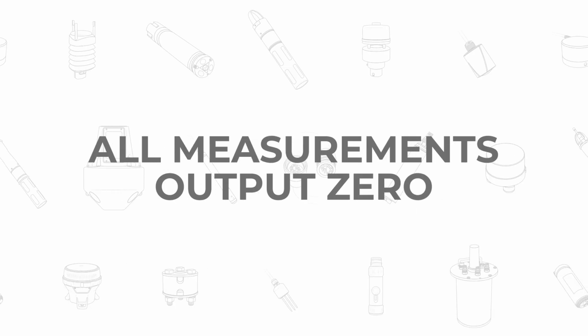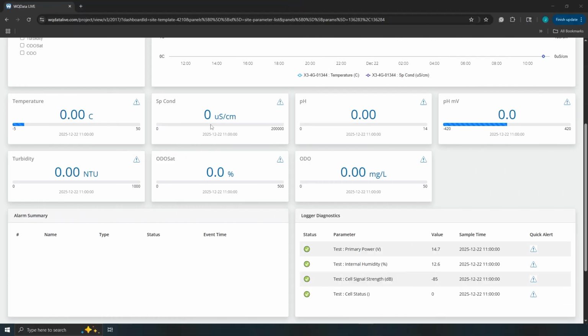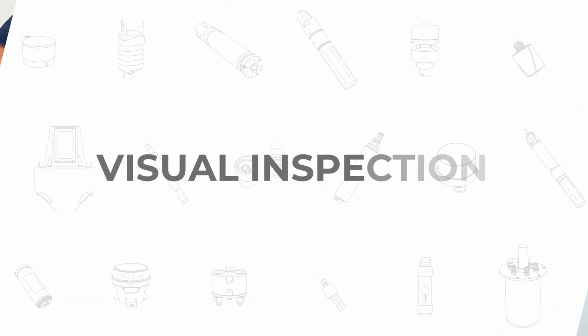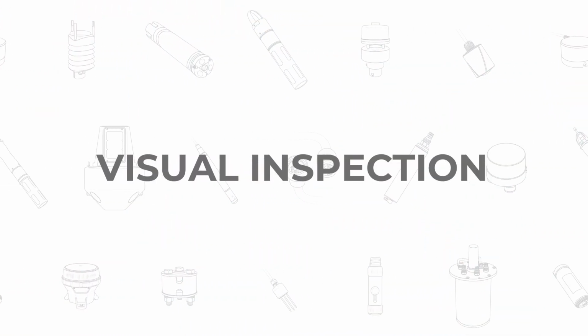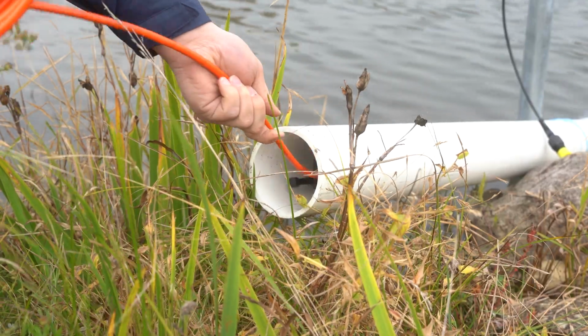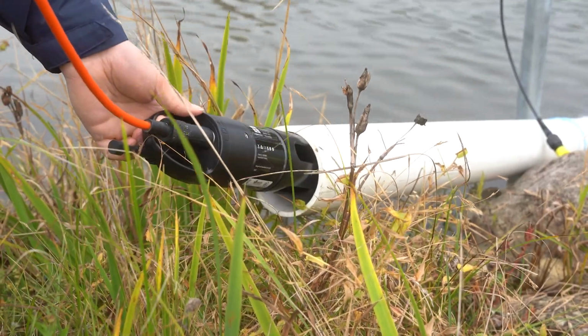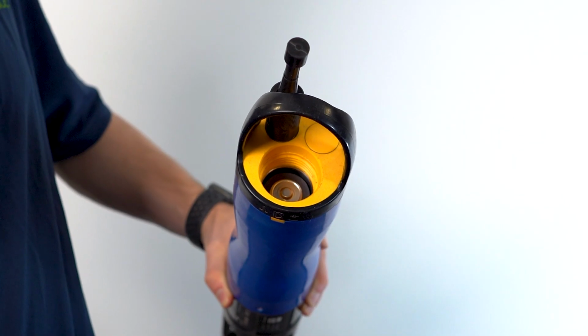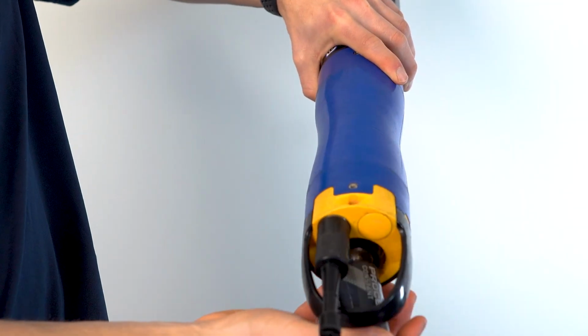If all Sonde measurements are reporting 0, there is an issue with one or more sensors and the Sonde should be inspected. Visit the field site and inspect the Sonde, cable connection, and power supply for physical damage. If installed, remove batteries from the Sonde.